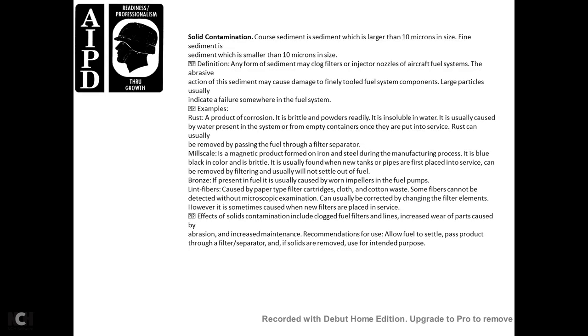Solid contamination consists of coarse sediment (particles larger than 10 microns) and fine sediment (smaller than 10 microns). Any form of sediment can clog filters, injection nozzles, and aircraft fuel systems. The abrasive action of sediment may cause damage to precision fuel system components. Large particles usually indicate a failure somewhere in the fuel system.